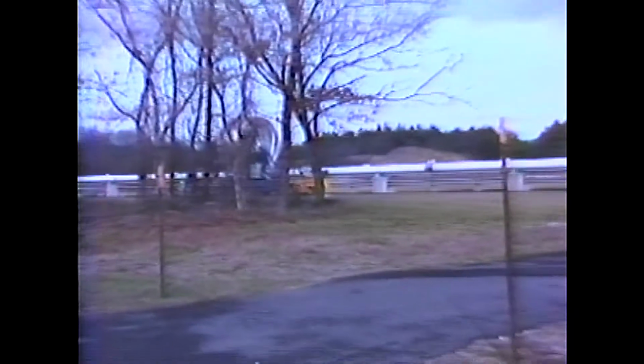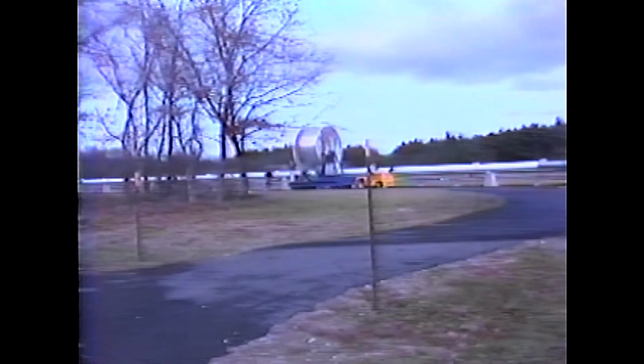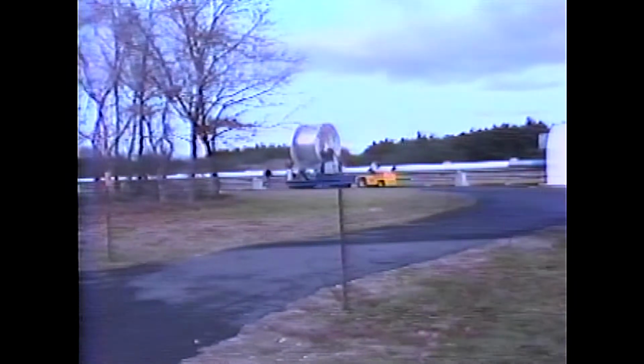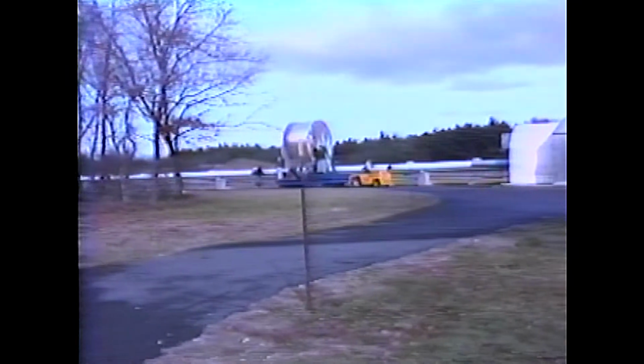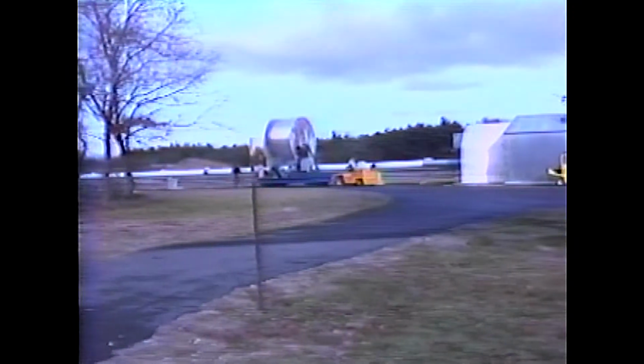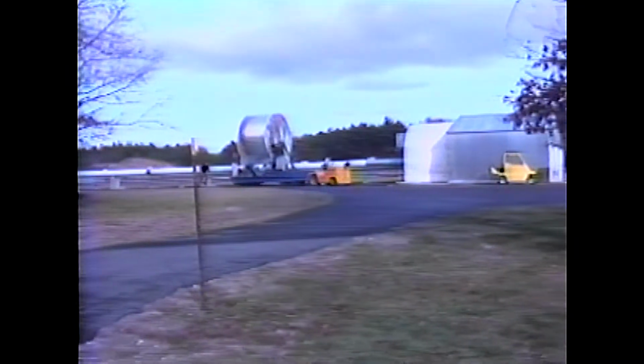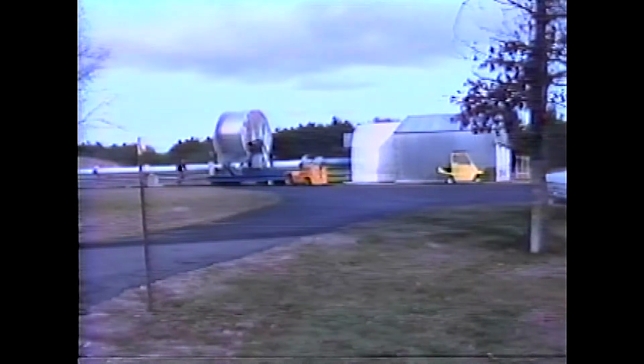The white pipe seen at the test facility is the cable enclosure. Normally, this would be underground, but at the test facility it is placed about 3 feet above the ground for easy accessibility. This pipe itself was the subject of several years' development in order to optimize the cost and thermal performance. The outside of the pipe is at ambient temperature, but inside, the cable is operating at a temperature of only 7 degrees or so above absolute zero.